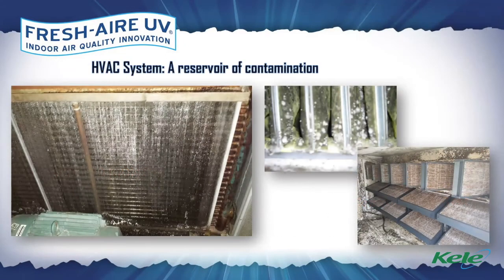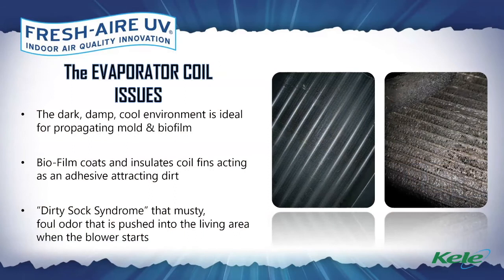So that brings us to piggyback off of my earlier point about the evaporator coil, which is addressing the HVAC system itself. And as we know, the coil is made up of tightly packed fins. Upon commissioning of the equipment, there is a microbial growth called biofilm that starts growing and insulating those fins. So as tightly packed as they are, once that biofilm starts growing, they become even more restrictive. You have heat transfer loss, airflow restriction, wear and tear. The system has to work harder in order to keep the conditioned air where the occupant wants it to be. It is a huge issue.